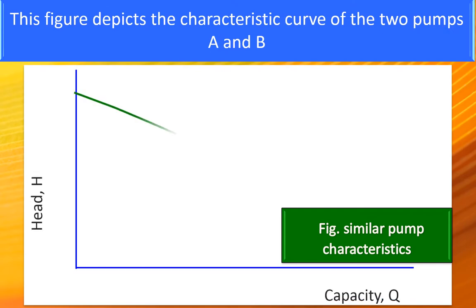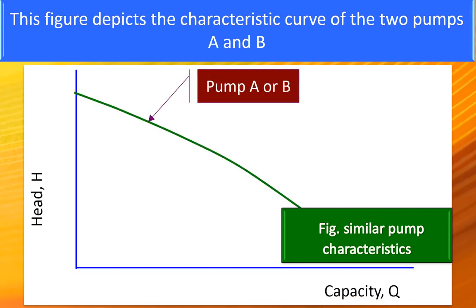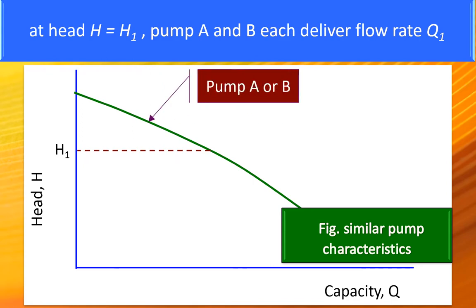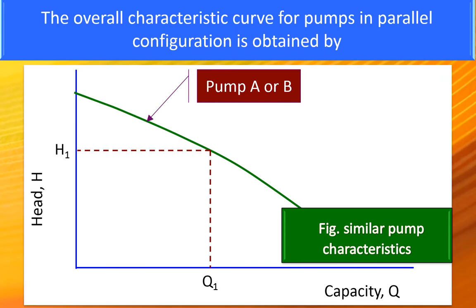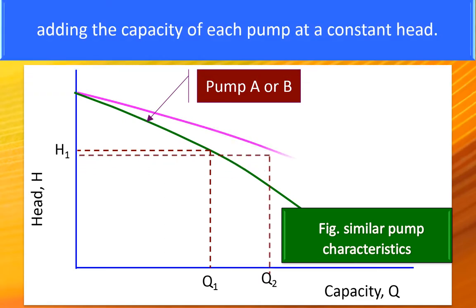This figure depicts the characteristic curve of the two pumps A and B. At H is equal to H1, the pump A and B each deliver the flow rate of Q1. The overall characteristic curve for the pumps in parallel configuration is obtained by adding the capacity of each pump at constant head.